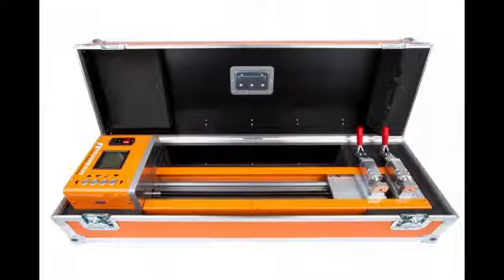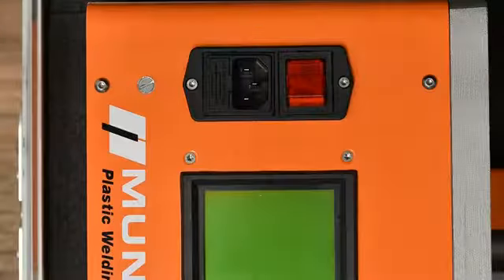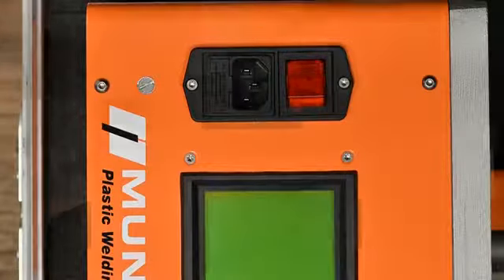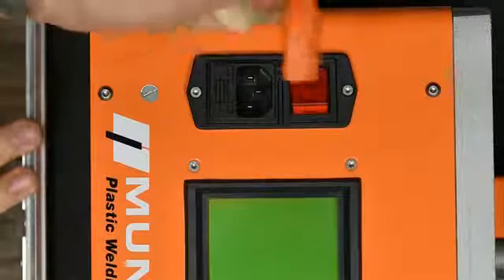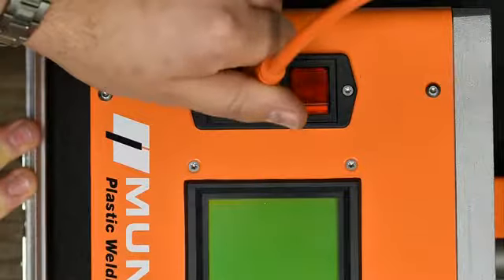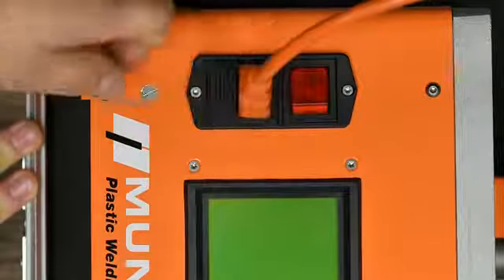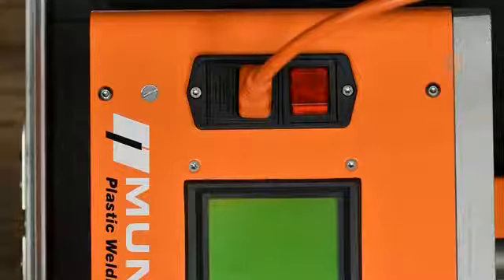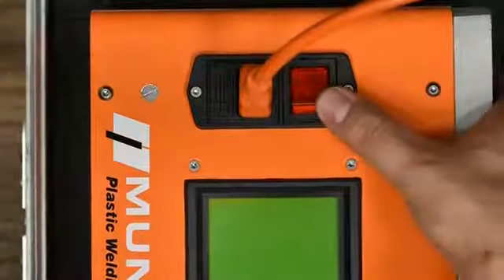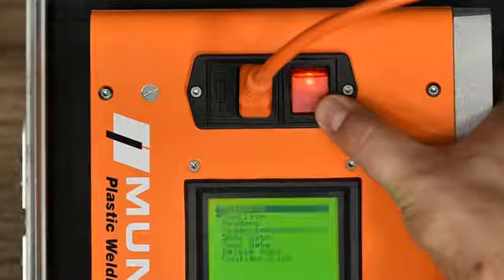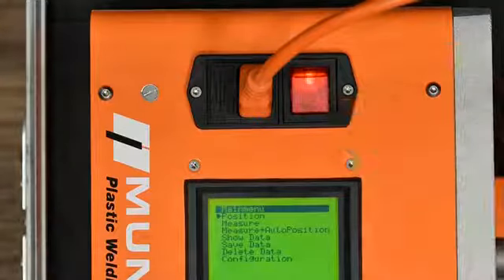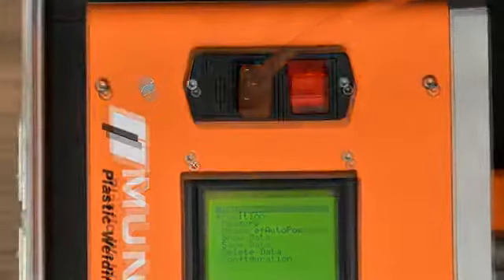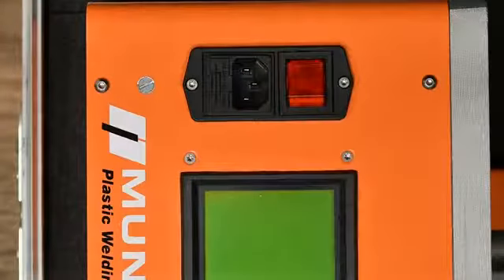This is the instruction video for Munsch's digital tensile tester Accura Dat. The machine comes with an international standard plug. Plug the mains cable into it and connect the cable to a 115 or 230 volts power supply. Now switch on the machine. The screen will light up and show the installed software version. Afterwards it will show the main menu.